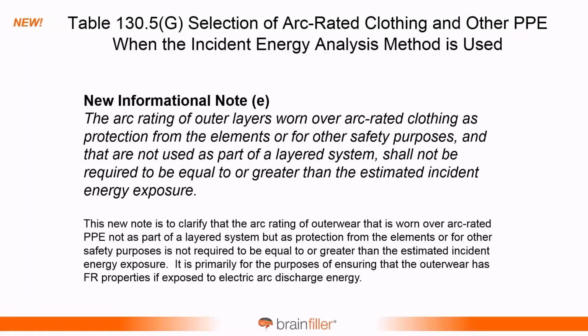So there have been a lot of questions about that over the years, and that was a change made to the 2021 edition of NFPA 70E. It specifically reads: the arc rating of outer layers worn over arc-rated clothing as protection from the elements or for other safety purposes, and that are not used as part of a layered system, shall not be required to be equal to or greater than the estimated incident energy exposure. So that's new. That's one of the additions.